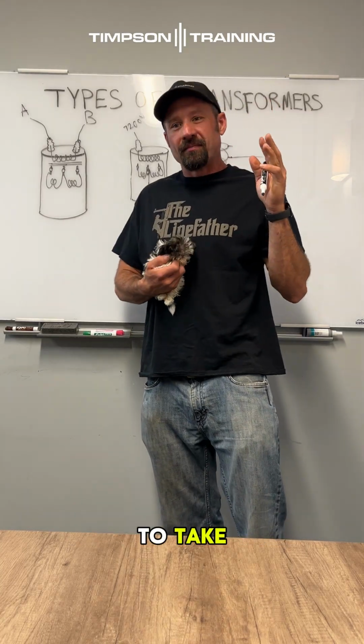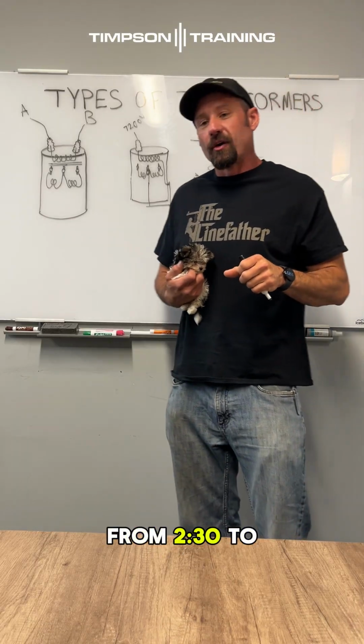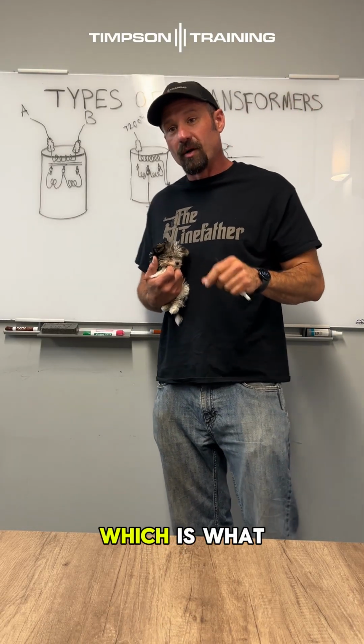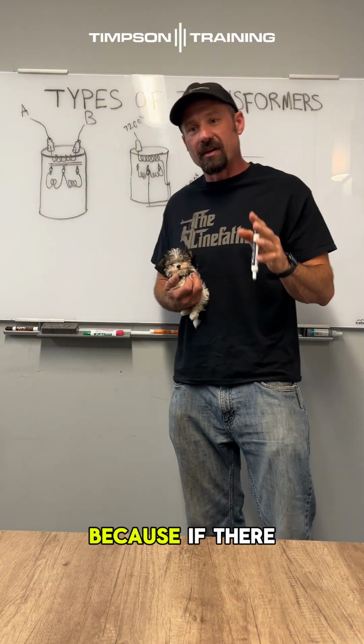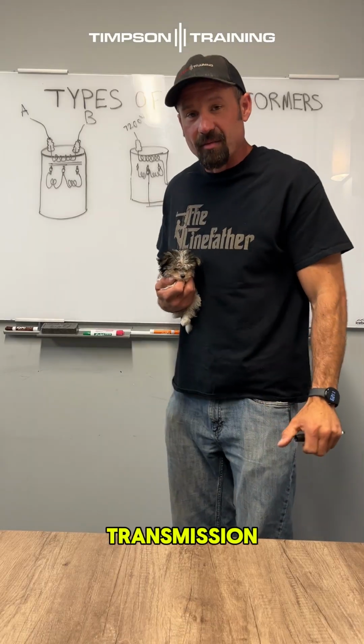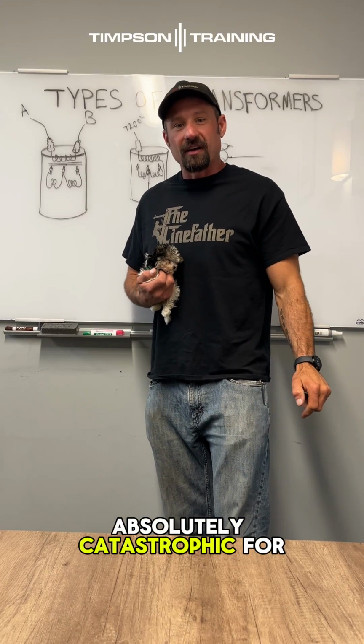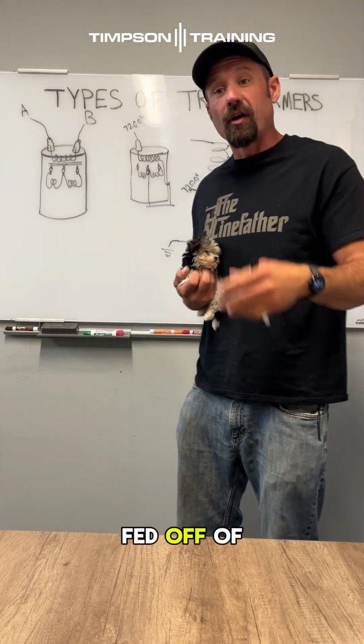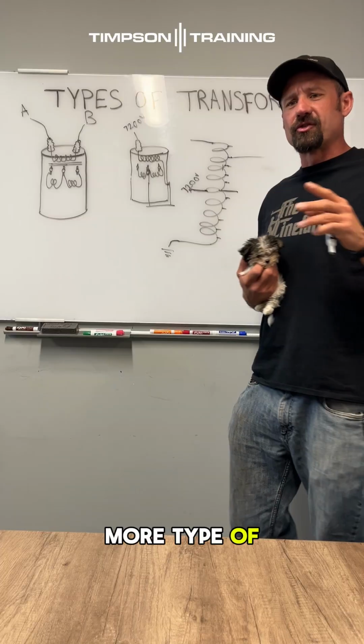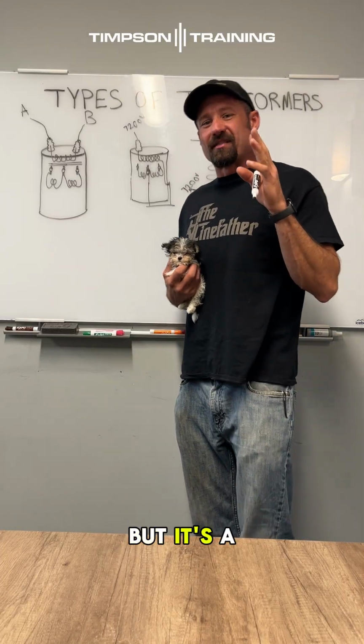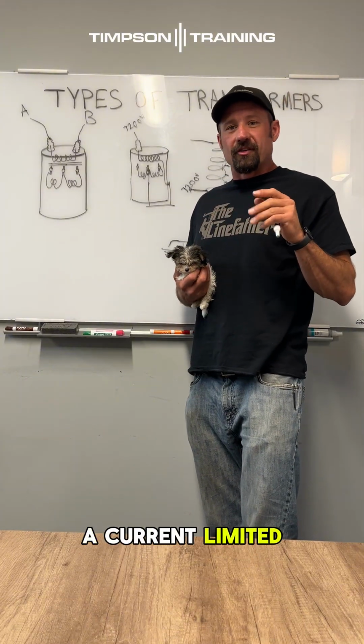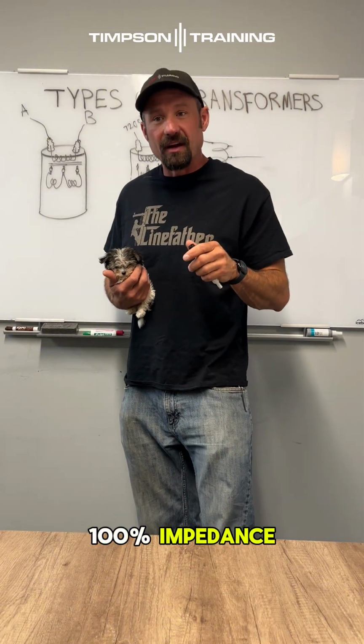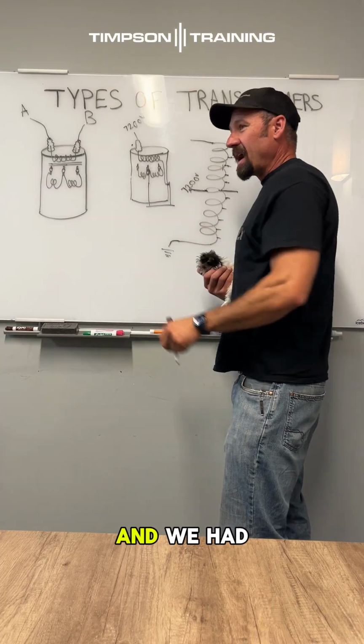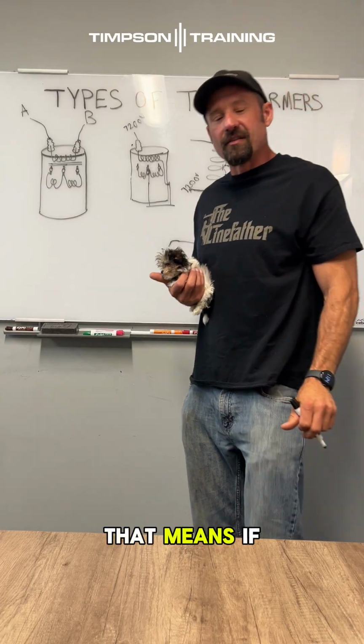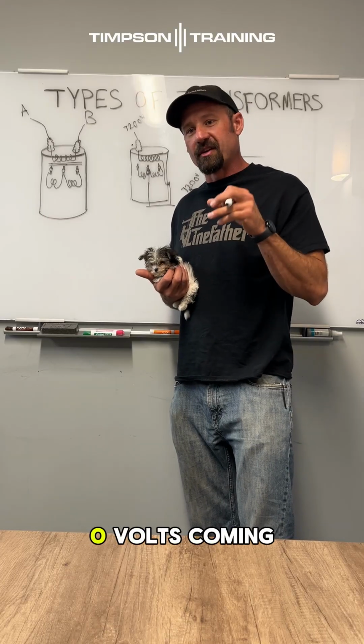So you wouldn't want to take and step your transmission voltage down from 230 to 12.47 with an auto transformer, which is what a regulator is. It's a type of auto transformer because if there was a power surge on the transmission, it would be absolutely catastrophic for the substation and the customers fed off of that substation. Now there's one more type of transformer. We're not going to get into it too much, but it's a current limited transformer. A current limited transformer means they're 100% impedance. So if you had a 7200 volt transformer and we had it set at 25 kVA, that means if you put a 25,000 watt load on there, you would have 0 volts coming out.